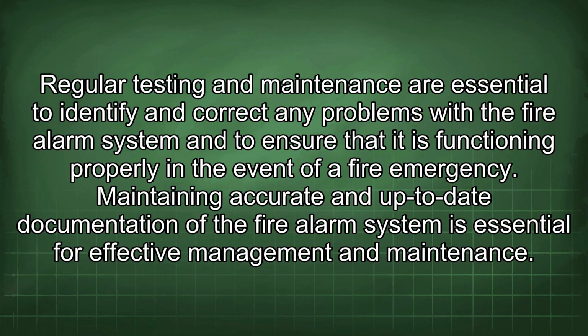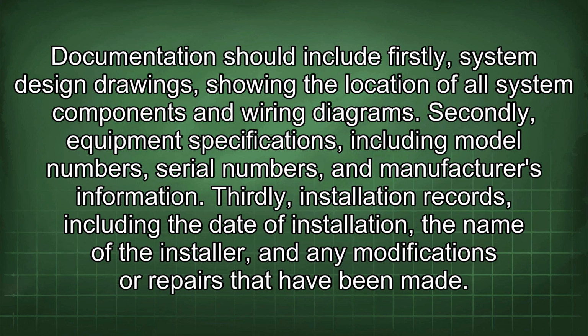Maintaining accurate and up-to-date documentation of the fire alarm system is essential for effective management and maintenance. Documentation should include: firstly, system design drawings, showing the location of all system components and wiring diagrams. Secondly, equipment specifications, including model numbers, serial numbers, and manufacturer's information. Thirdly, installation records, including the date of installation, the name of the installer, and any modifications or repairs that have been made.